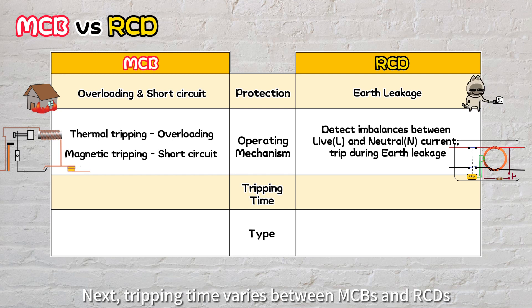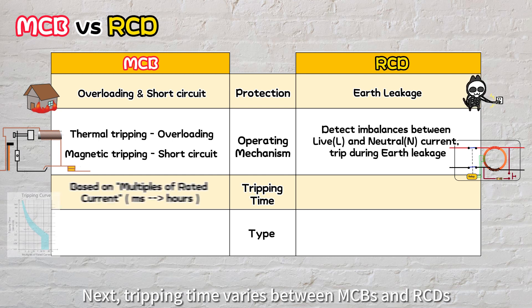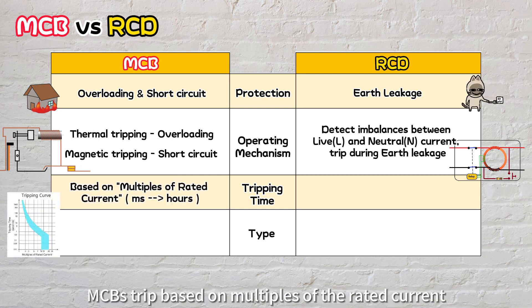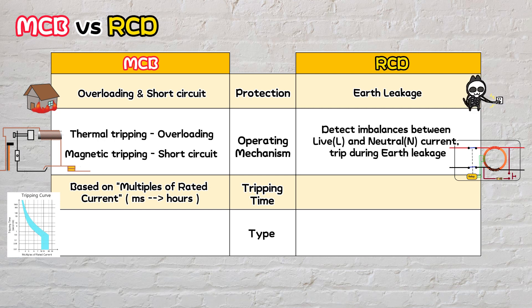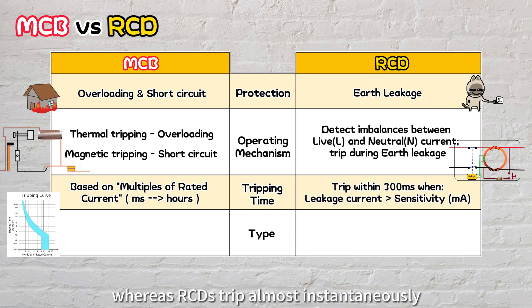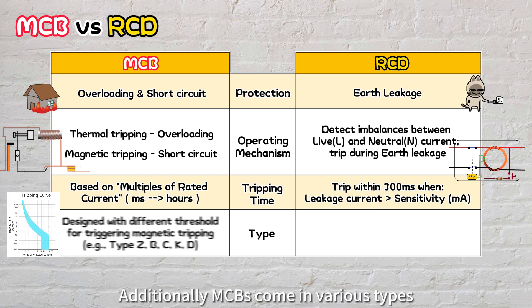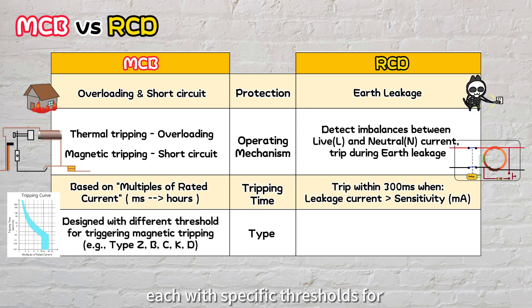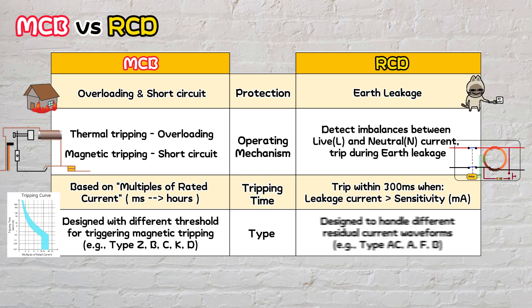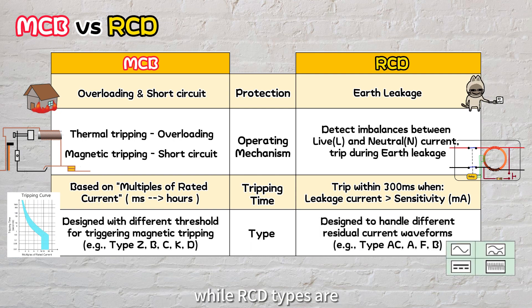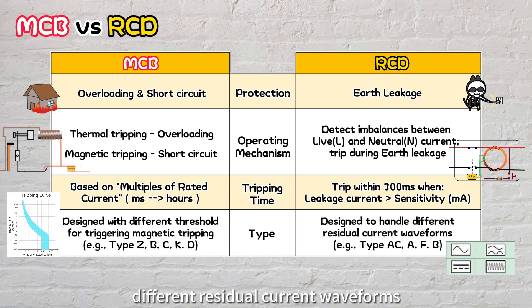Tripping time varies between MCBs and RCDs. MCBs trip based on multiples of the rated current, ranging from milliseconds to hours, whereas RCDs trip almost instantaneously, triggered when leakage current surpasses the sensitivity rating, typically within 300 milliseconds. Additionally, MCBs come in various types, each with specific thresholds for triggering magnetic tripping, while RCD types are designed to handle different residual current waveforms.